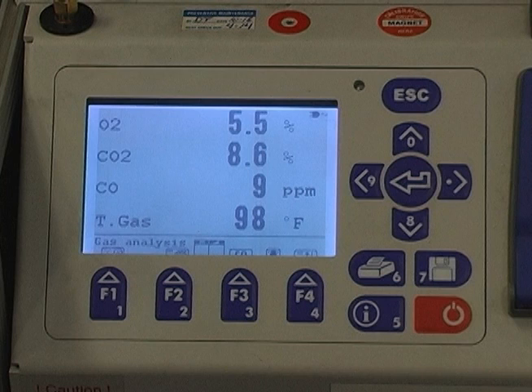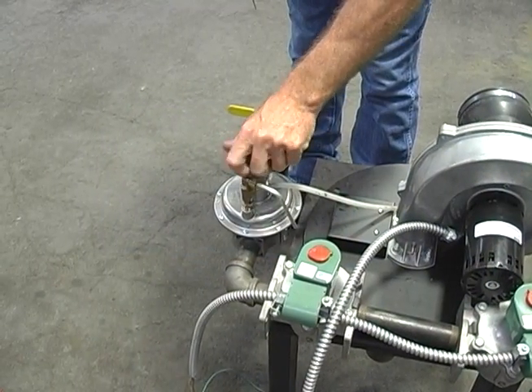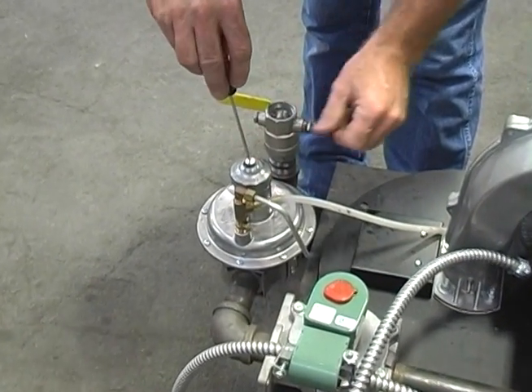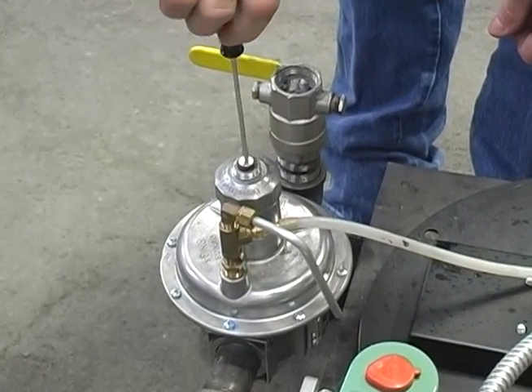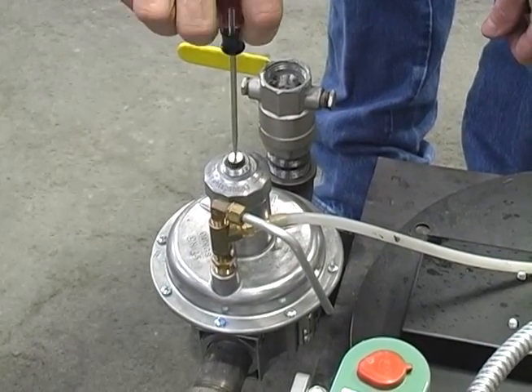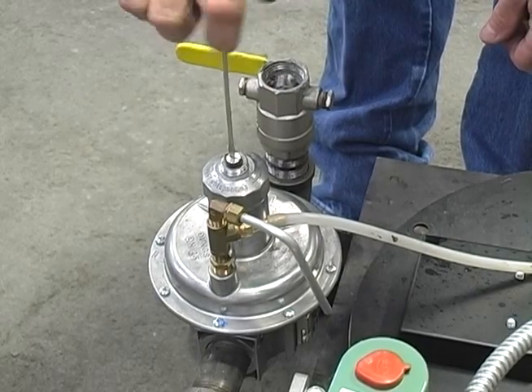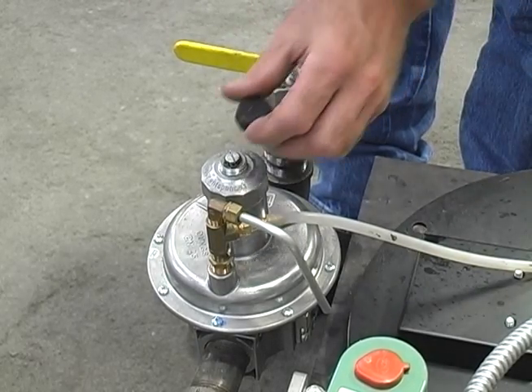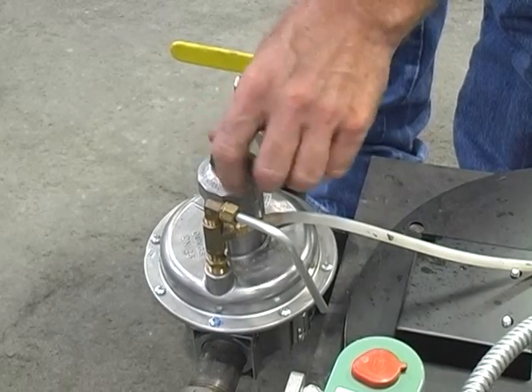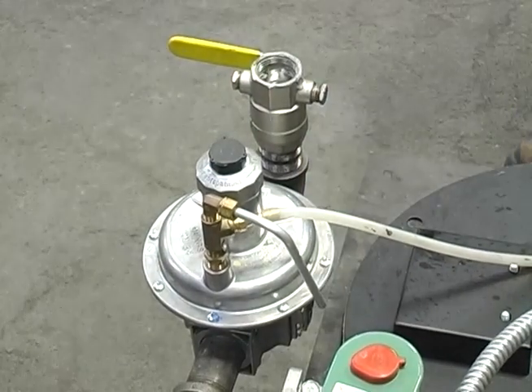At low fire, the carbon dioxide level must be between 8.5% and 9.5% for natural gas, and between 9.5% and 10.5% for LP gas. If the level is in this range, no adjustment is required or recommended. If the CO2 level must be adjusted, the low fire adjustment is made at the gas regulator. With the burner firing, adjust the regulator screw clockwise to increase gas flow and increase CO2. Adjust the regulator screw counterclockwise to decrease gas flow and decrease CO2.